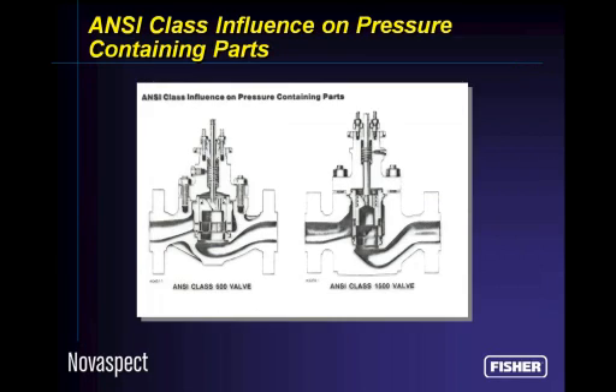Another very important aspect of design of a control valve is the ANSI class. It has influence on the pressure containing parts. You have a design pressure and a design temperature for any piping system. The valve, being a part of the piping system, of course, has to obey the same design requirements as the pipeline that it's installed in. So you can usually go to your piping design documentation and find what the ANSI class is for any valve in the system.